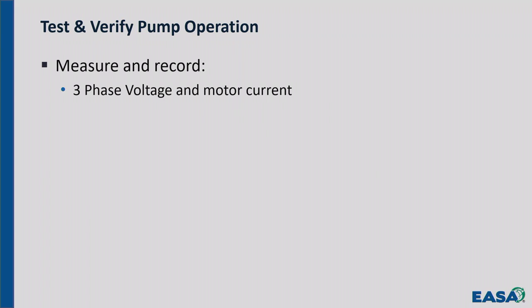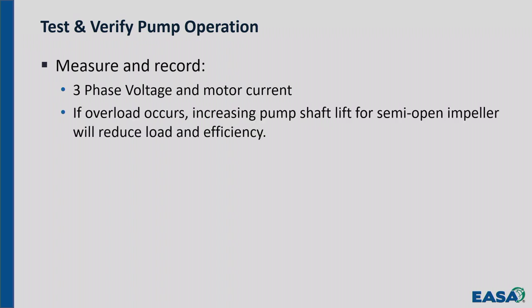All right. The other things that are critical, once you get it running, you want to record all the electrical data. You want to know your voltage and current on all 3 legs. If an overload occurs and it's a semi-open impeller, you could raise that shaft up a little bit. That'll change the efficiency of the pump. They won't get as much fluid out of the pump as they would normally, but if it's overloading the motor, that may be what's necessary.